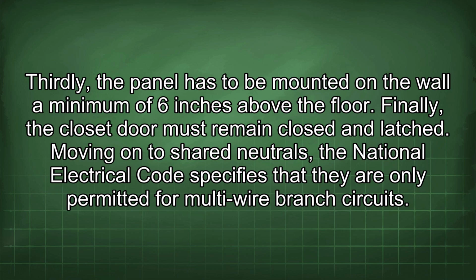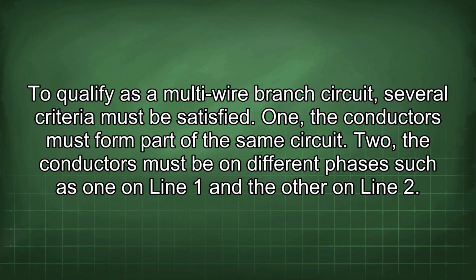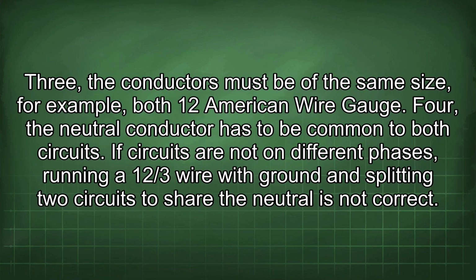Moving on to shared neutrals, the National Electrical Code specifies that they are only permitted for multi-wire branch circuits. To qualify as a multi-wire branch circuit, several criteria must be satisfied. 1. The conductors must form part of the same circuit. 2. The conductors must be on different phases, such as one on line 1 and the other on line 2. 3. The conductors must be of the same size, for example, both 12 American wire gauge. 4. The neutral conductor has to be common to both circuits.